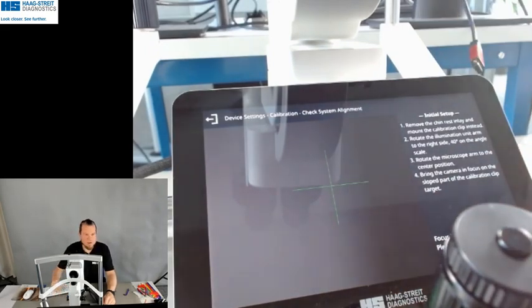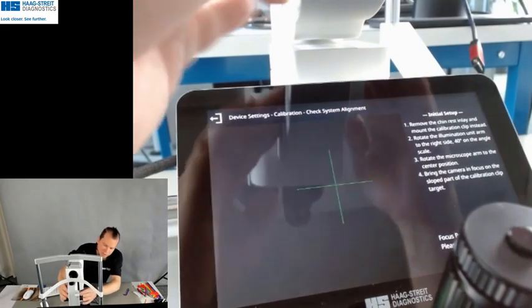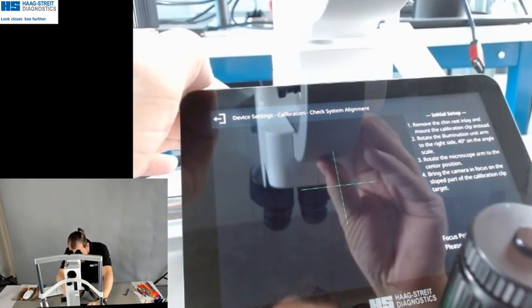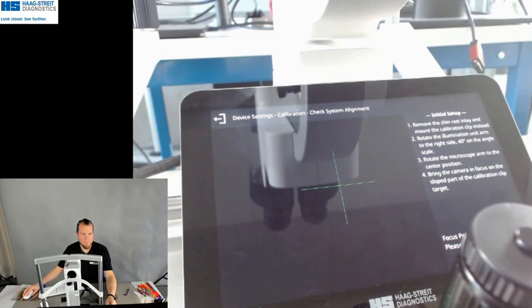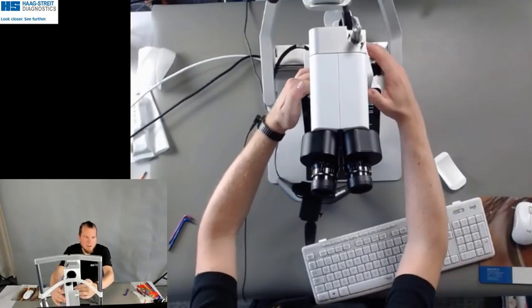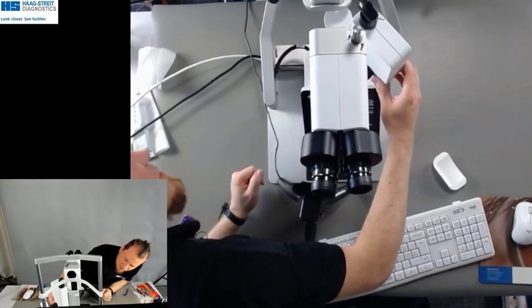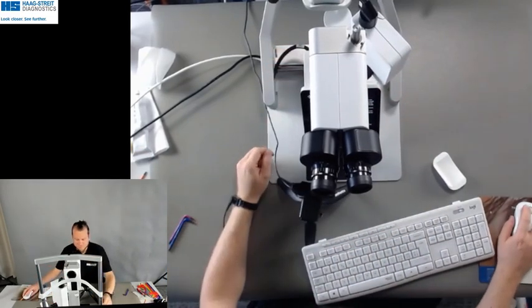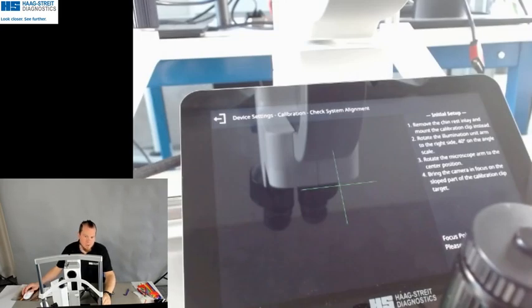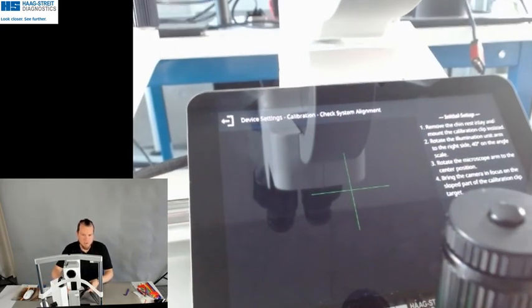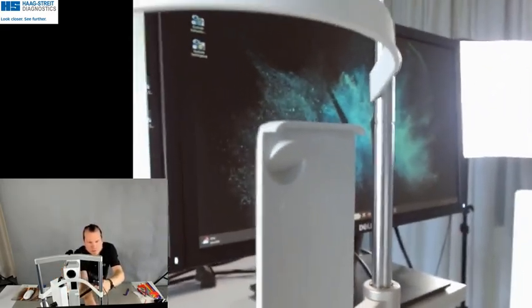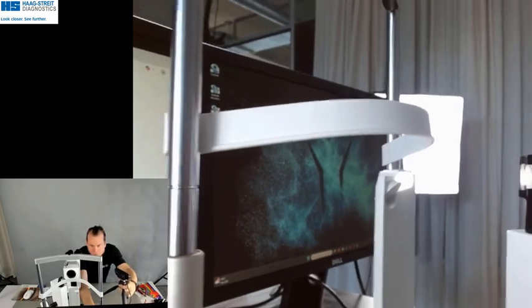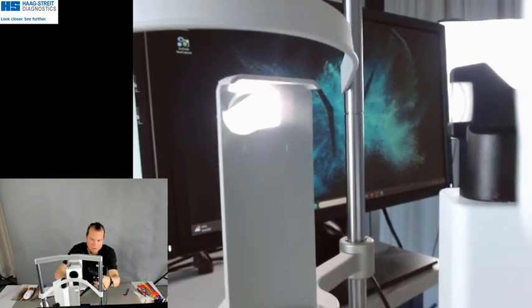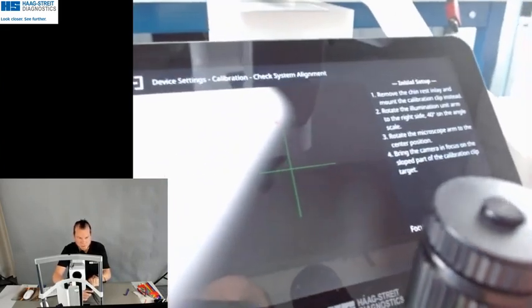Now we follow the instructions on the screen, rotate the illumination to 40 degrees, make sure the microscope is nicely straight aligned. So we move our illumination 40 degrees to the side. For this you have an index ring at the front. Now we need to focus onto the sloped surface on this check gauge. For this we first align the check gauge in the height of the patient's eye, and now we move it into the view. From there on we can switch to the screen and follow the instructions.